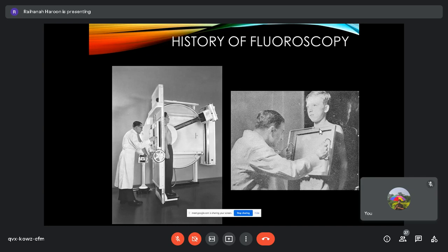But for X-ray, for example, the function is called acquire, capture, which means that we take the X-ray image at full dose. But a fluoroscopy machine has a function that we call screening. That's why if you go to a fluoroscopy room, there will be a pedal. If the radiology MO is going to take the image, it's like making a video.